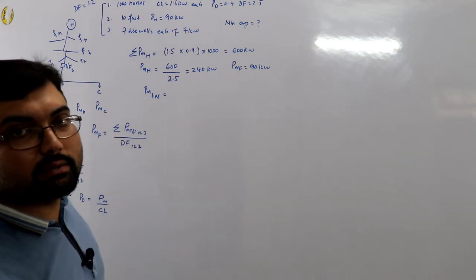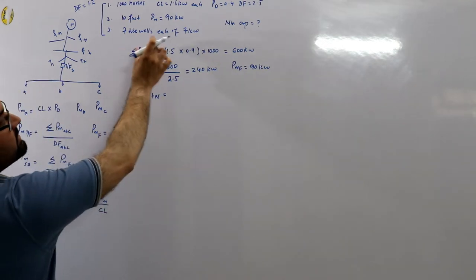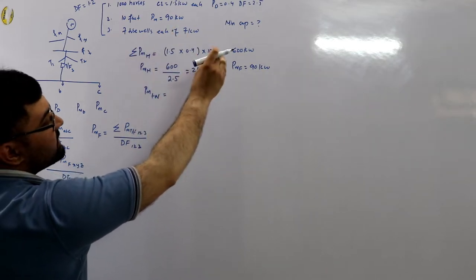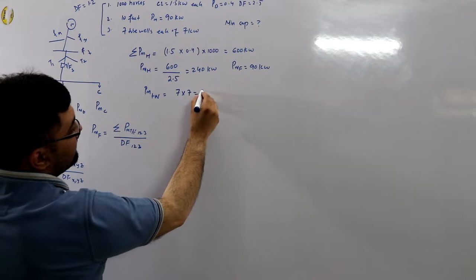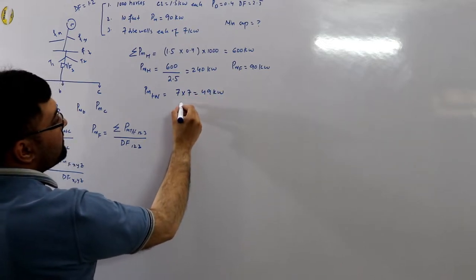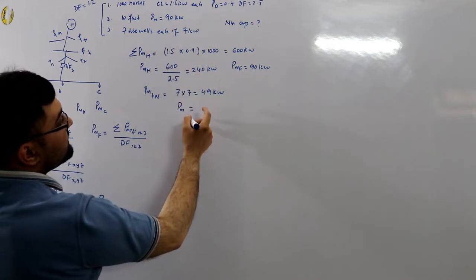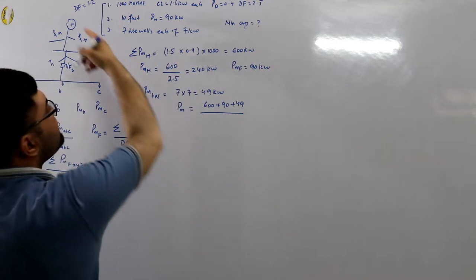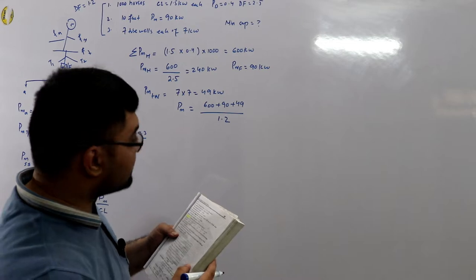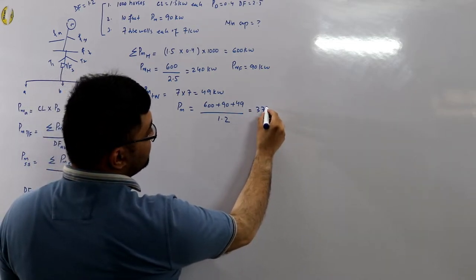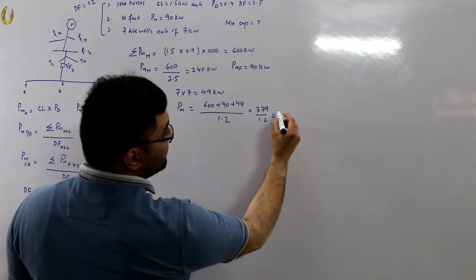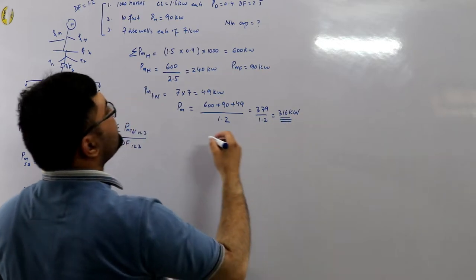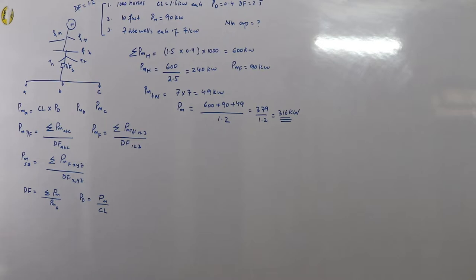The maximum demand of the overall area is the summation of maximum demands divided by the overall diversity factor: (240 + 90 + 49) / 1.2. Wait — using 600 before diversity: (600 + 90 + 49) / 1.2? Correcting: the sum is 379 / 1.2 = 316 kilowatts. This is the minimum capacity of the power station, equal to the maximum demand of the area. This was example 3.9.